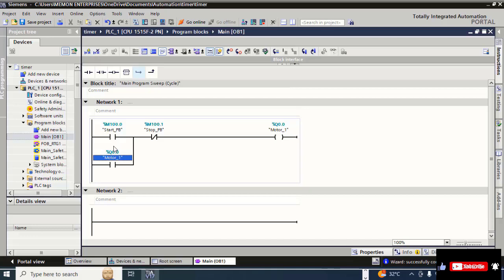This first network is now completed. When you press the motor start button, the motor will start, and when you release this push button, the motor will be latched via contact Q0.0.